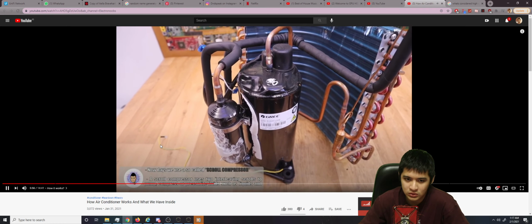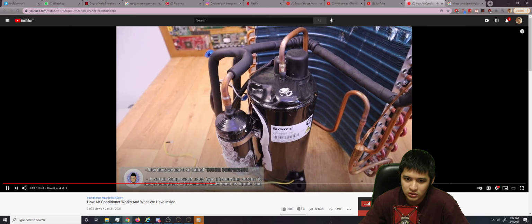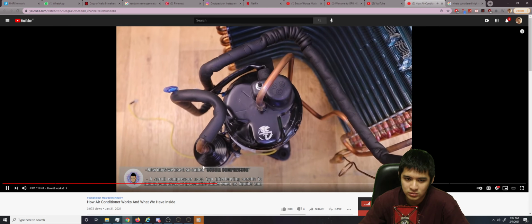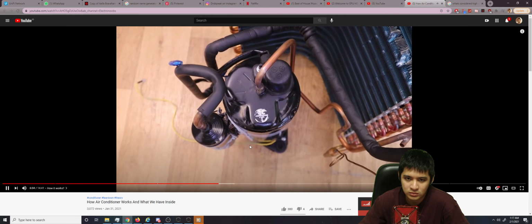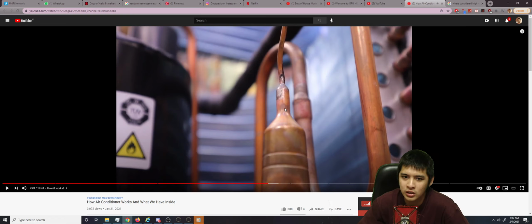Container in order to prevent leaking and also reduce the noise. Nowadays we use a scroll compressor instead of a basic piston compressor. The basic one consists of a motor. Okay, where is that one where he showed the compressor? Smaller diameter in order to restrict the refrigerant flow. That is correct. That's how capillary tube works. It's not variable, it's a fixed metering device. While TXV is, what is it? Some people call it variable. It depends on the temperature of the suction and stuff.